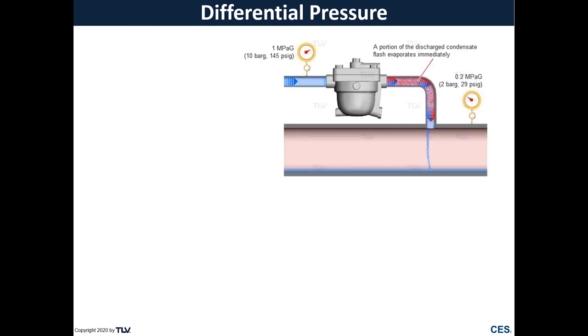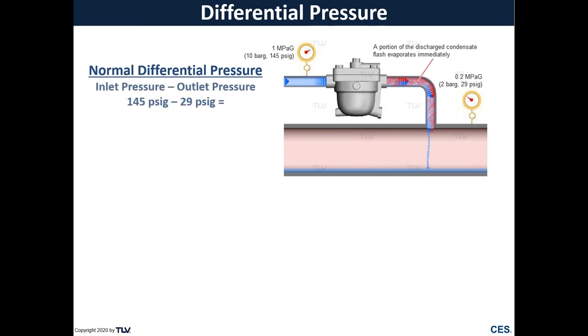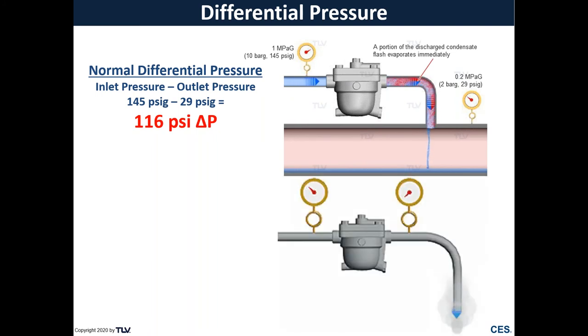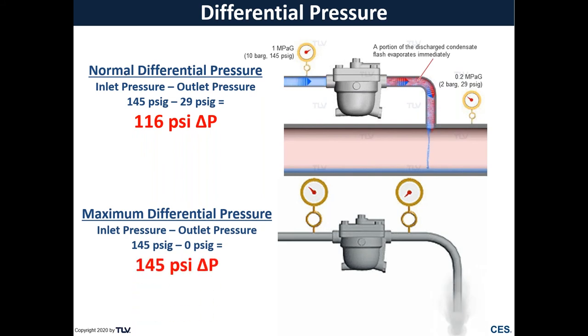Now, the second important piece when sizing a steam trap beyond our condensate load is our differential pressure. So if we look at a steam trap example, a trap discharging from 145 psi into a return header running at about 29 psi, our normal differential pressure is going to be our inlet pressure minus our outlet pressure, or in this instance, about 116 psi differential. But that is not our maximum pressure differential. If we were to take that same application and discharge it to atmosphere, now our maximum pressure differential is actually 145 psi. So we want to make sure that we're selecting a trap that will both discharge at our maximum pressure differential and yet still have enough capacity at what our normal or our minimum pressure differential may be.